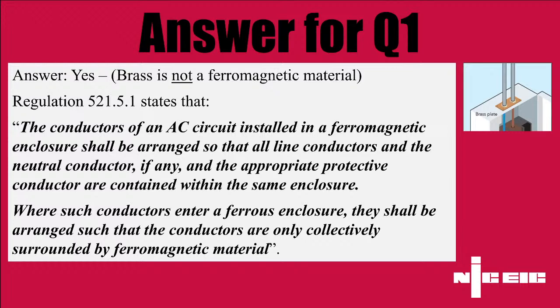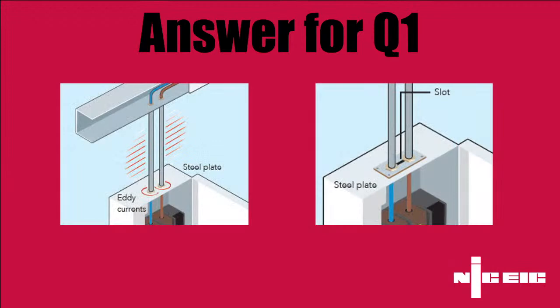You would commonly see this in a lot of big industrial and commercial installations where this has been used. And if it was on an assessment and we saw line and neutral conductors separated going into a ferromagnetic enclosure, we would raise that as a departure and as a non-conformance as a result.